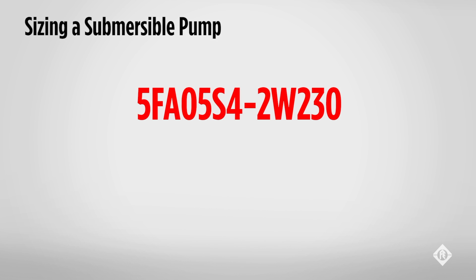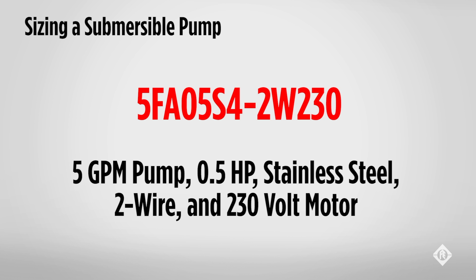As you start to shop around, you will see a pattern in the model numbers of submersible pumps. They usually give materials, type of construction, horsepower, and flow rate. For example, a 5FA05S4-2W230 stands for five gallons a minute, half horsepower, stainless steel with a two-wire 230-volt motor. The fact that the pump is declared to be five gallons a minute doesn't mean that it can't pump more or less than that. It is just most efficient at that flow rate.